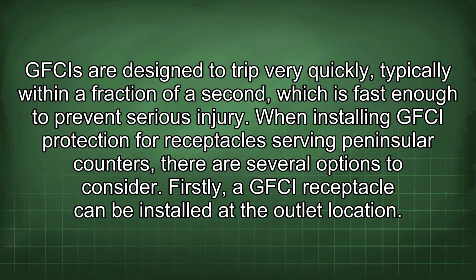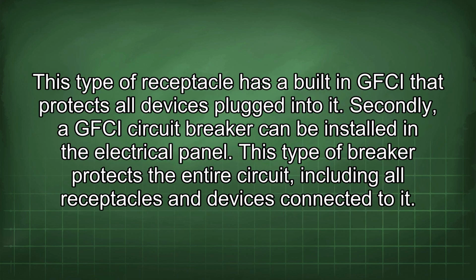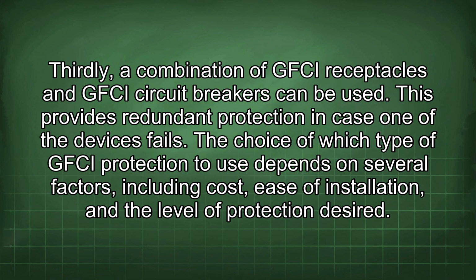Firstly, a GFCI receptacle can be installed at the outlet location. This type of receptacle has a built-in GFCI that protects all devices plugged into it. Secondly, a GFCI circuit breaker can be installed in the electrical panel. This type of breaker protects the entire circuit, including all receptacles and devices connected to it. Thirdly, a combination of GFCI receptacles and GFCI circuit breakers can be used. This provides redundant protection in case one of the devices fails.